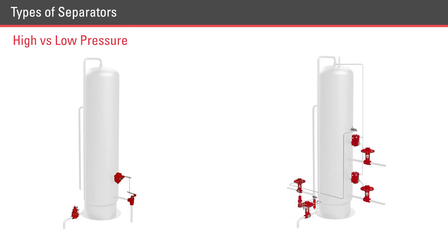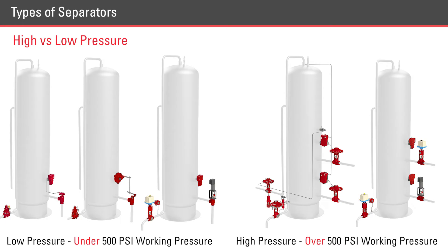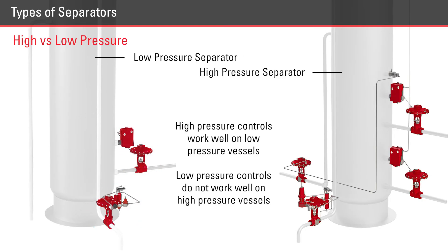Separators can be high or low pressure. Anything under 500 psi is considered low pressure, and anything above 500 psi is considered high pressure. There are times that you have to look closely to see the differences between high and low pressure vessels. One confusing factor is that high pressure controls are sometimes needed on low pressure vessels in order to have proper control. High pressure controls can work well on low pressure vessels; however, low pressure controls do not work well on high pressure vessels.